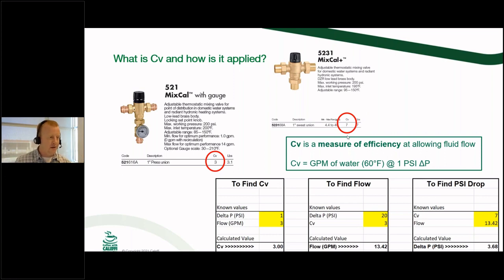Now, this is where people get into trouble. They call up the wholesaler and say, hey, I need a 1-inch mixing valve. And the wholesaler says, well, let me look for you. Let's see what we've got for you. I've got this mixing valve here, this 521616A. This will be your 3/4 inch press, or 1-inch press, excuse me. And then I've got this 523168A. This was 1-inch sweat, but they also have it in press too. And the wholesaler, maybe he knows, maybe he doesn't know, but the contractor doesn't know. They're just on the phone. They say, well, what's the cost? And this is where people are going to really step in it.